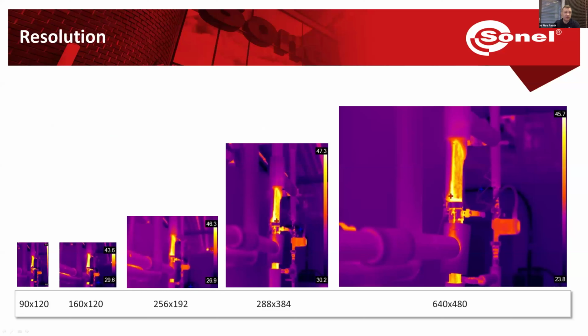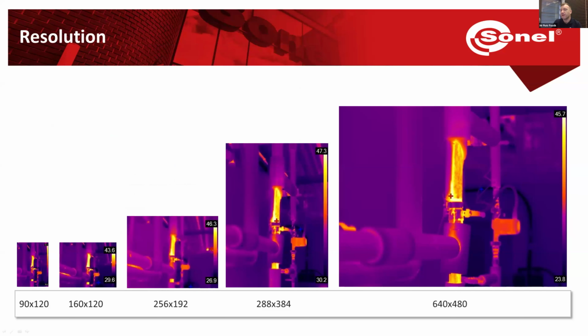Then the next thing which is important about the camera and the size of the picture. So this is the infrared resolution. And here you have some examples from 90 by 120 pixels up to the big one, 640 by 480 pixels. But let's remember that the number of pixels does not only work for the size of our image, but also we have temperature values for each and every pixel. So for example, let's take something here in the middle, 256 pixels by 192. That gives us actually nearly 50,000 points with temperature reading. Yeah, so that's a lot of points.